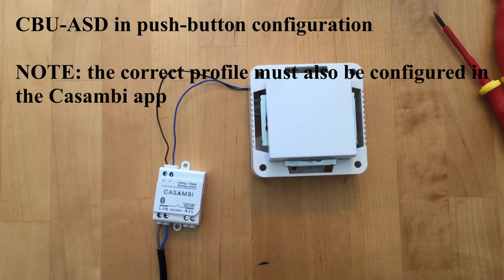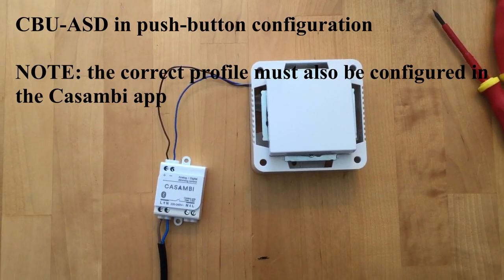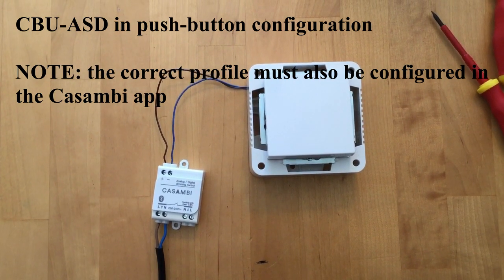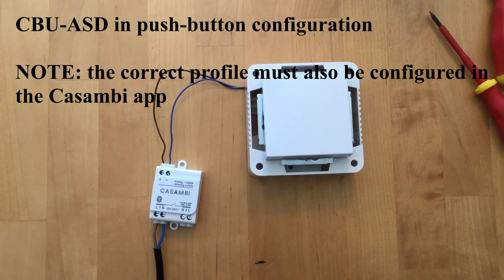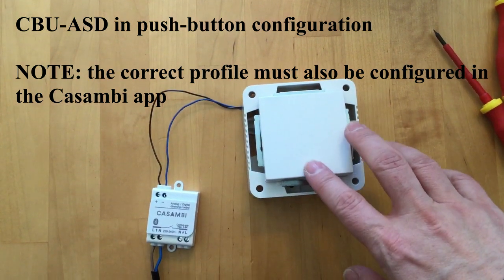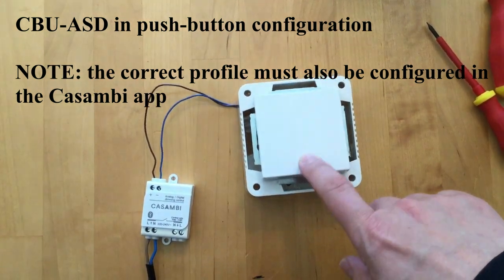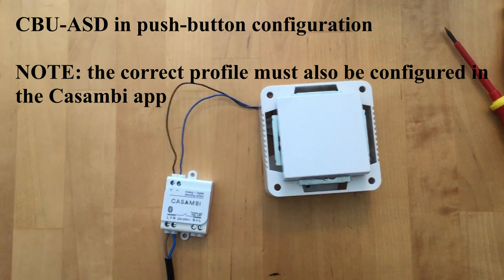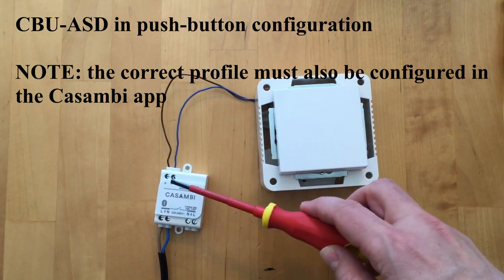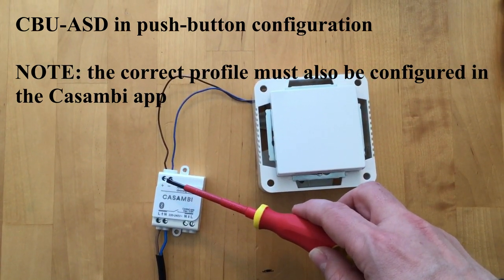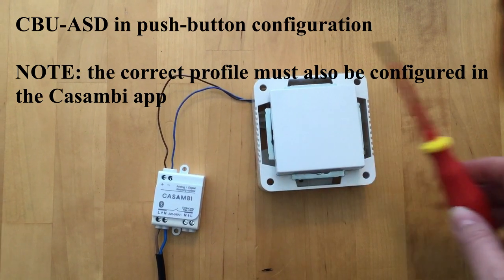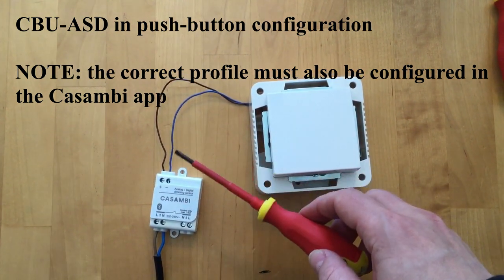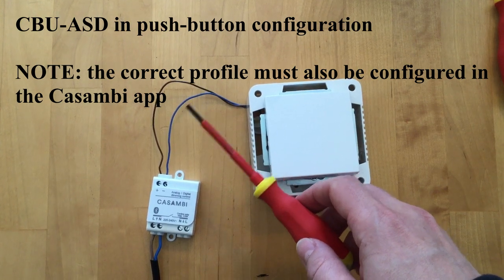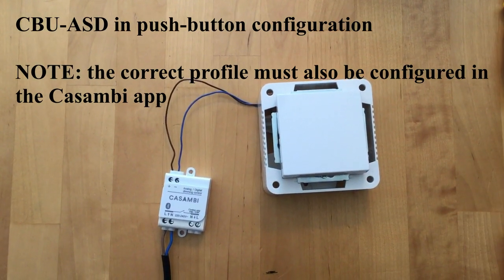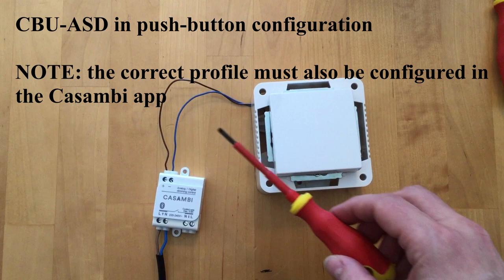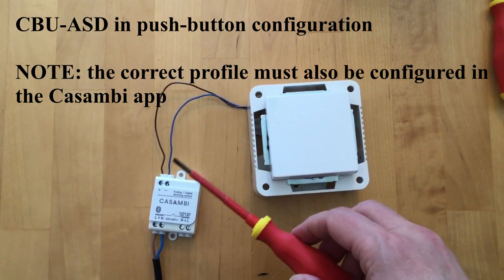This is a very quick example of how the Casambi CBU-ASD should be configured to be used as a push button. This is a regular, momentary push button, and it's configured to the analog digital ports of the CBU-ASD. Although here the wires are shown as blue and brown, representing line and neutral, there isn't actually any current going through them. It's simply connecting the circuit.